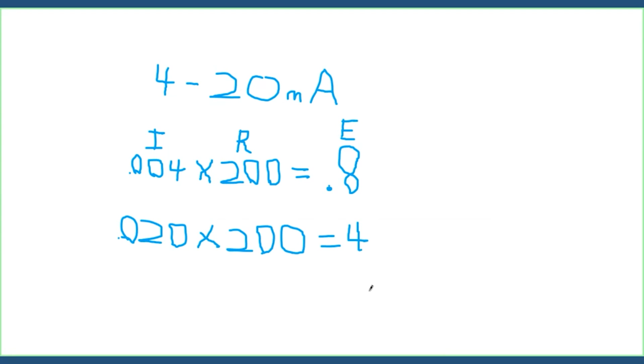Another common place we do this is with speed control on governors. We put out a 4 to 20 milliamp signal, except we substitute the 200 ohm resistor with a 250 ohm resistor. And if we do the same math formula, 4 milliamps times 250 is going to equal 1 volt, and 20 milliamps times 250 is going to equal 5 volts. So we can drive a 1 to 5 volt signal with a 4 to 20 milliamp signal source.